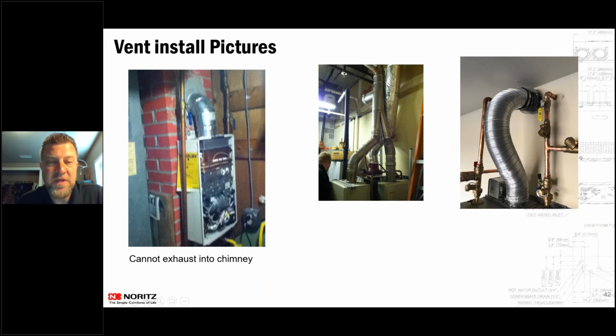Yeah, so inside of that chimney, those units have fans that are running and pushing. If that chimney is not ventilating out properly and it starts causing back pressure in there and that fan can't exhaust, it's going to start pushing flue gases inside the house. Gotcha. So they want to have that chimney kit put in the chimney so it's venting correctly out of there. Because a lot of those chimneys have caps that aren't letting it vent correctly. They weren't built for that pressure of that fan pushing the flue gases up and out. Gotcha, thank you.